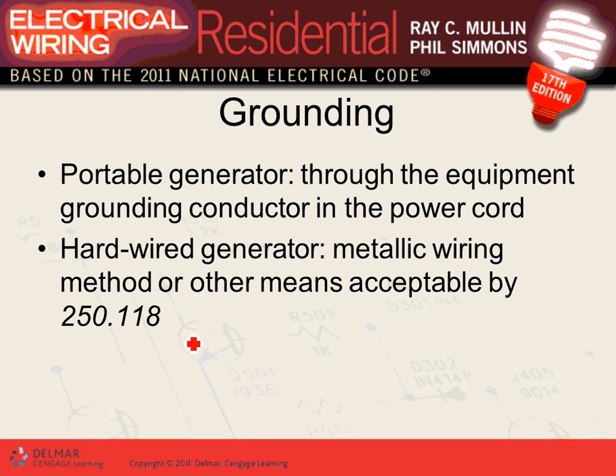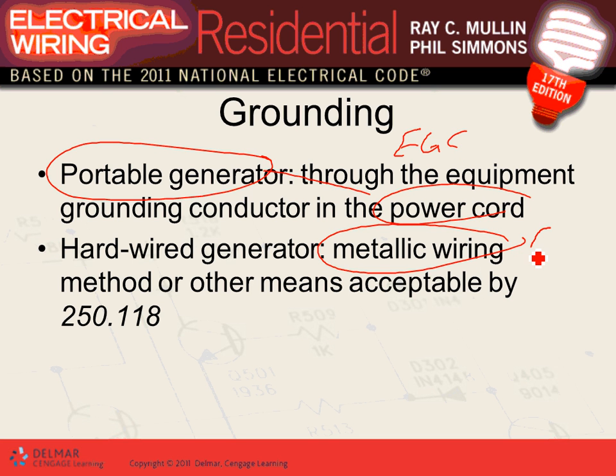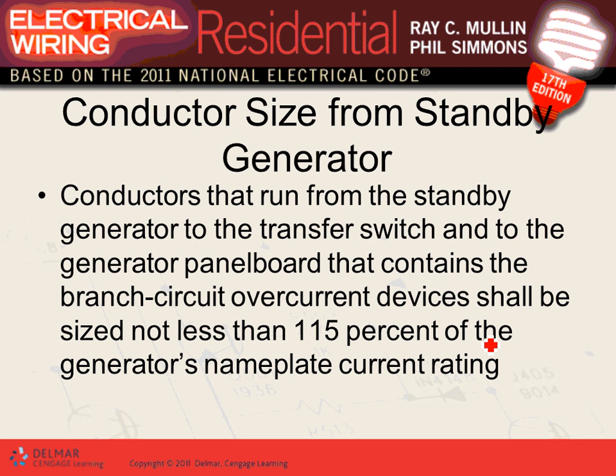Grounding. Portable generators, guys, are grounded through the cord. If you have a portable generator, all your grounding system is happening through the cord because you have an equipment grounding conductor in the cord. Hardwired generators, if you're using metallic wiring, EMT, that will be your grounding method, or you have to pull an equipment grounding conductor with it. So when you tie your generator through a cable, your cable has to have two hots, neutral, and a ground. When you put a conduit between the generator and the panel or the transfer switch, you have to have four conductors in it: two hots, neutral, and an equipment ground conductor. If it's PVC, if it's rigid or EMT, that will work for you.